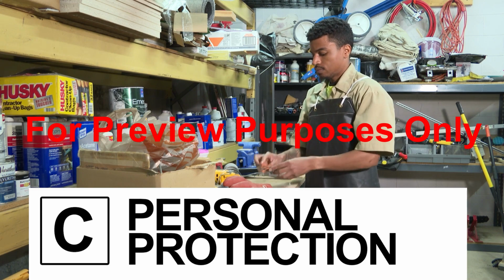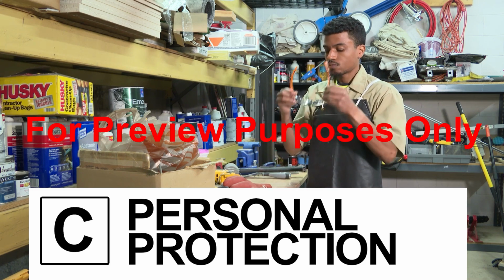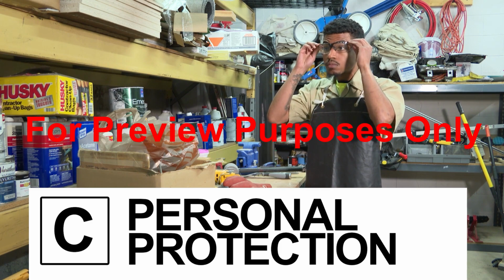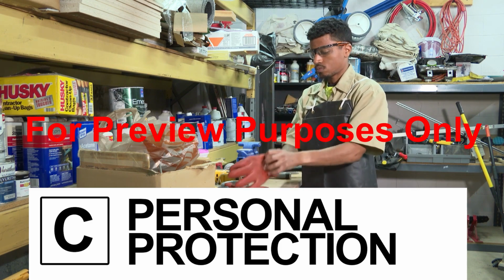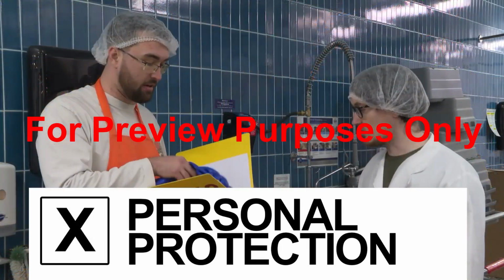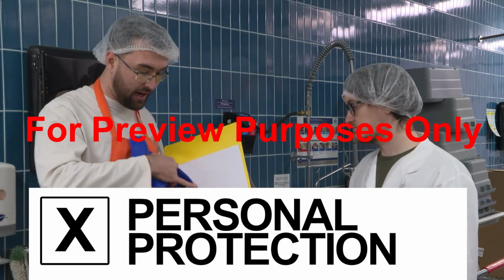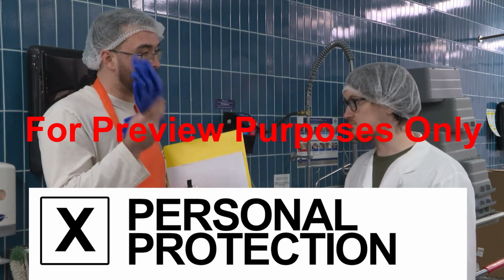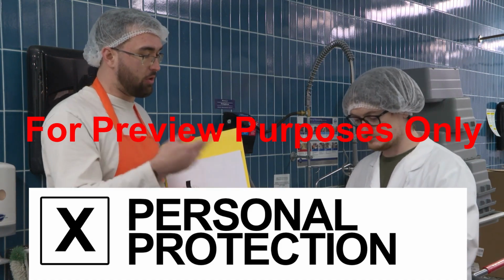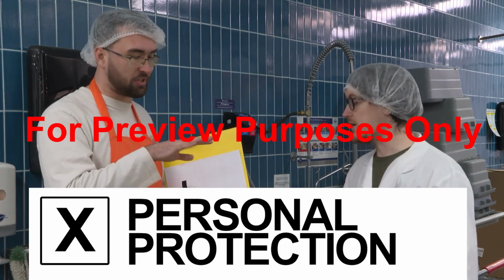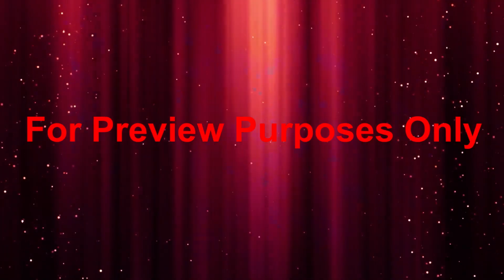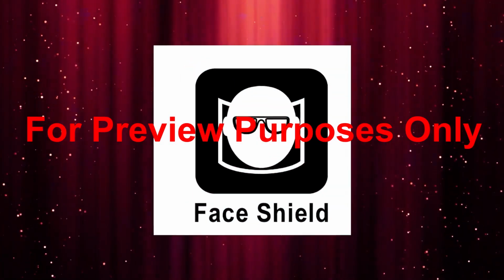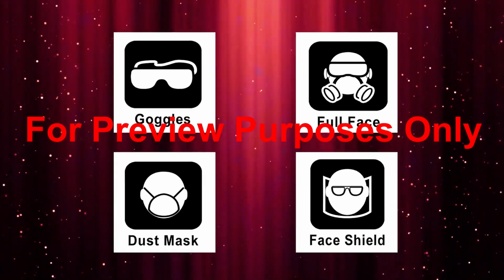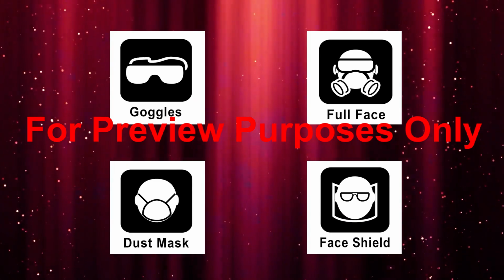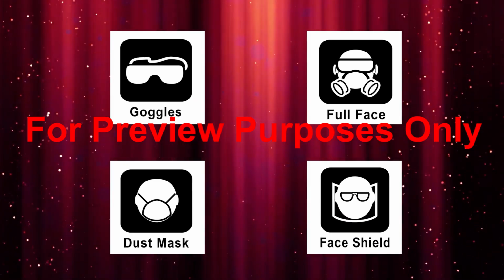For instance, the capital letter C indicates that safety glasses, gloves, and a synthetic apron should be worn when working with the material. If the personal protection column is marked with an X, special handling is required, in which case you will need to get additional information from the material's SDS or your supervisor. Some variations of the HMIS system use pictograms instead of letters to show what PPE should be worn, which makes it even easier to determine what you need.